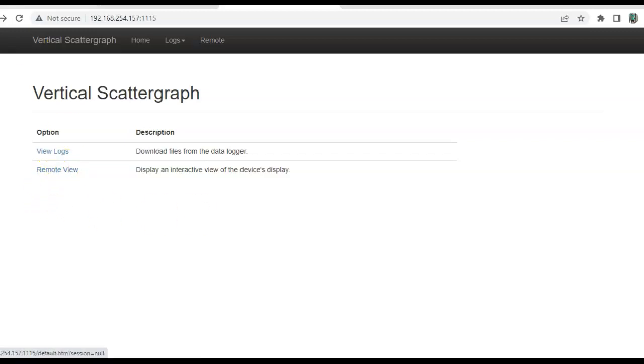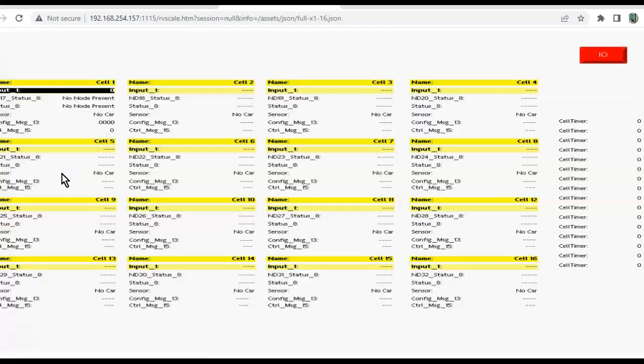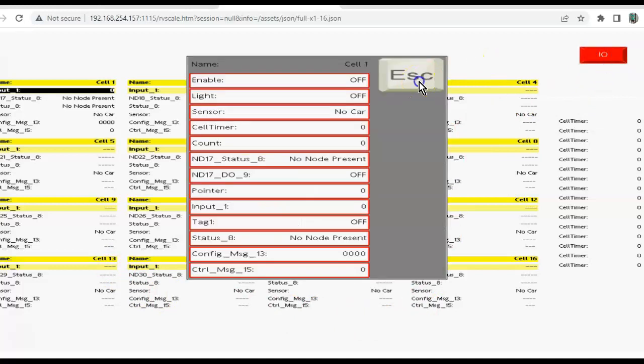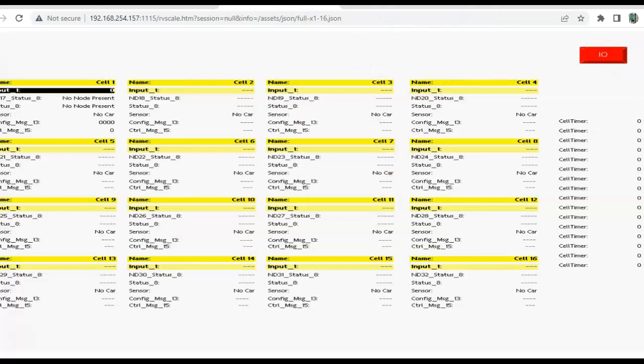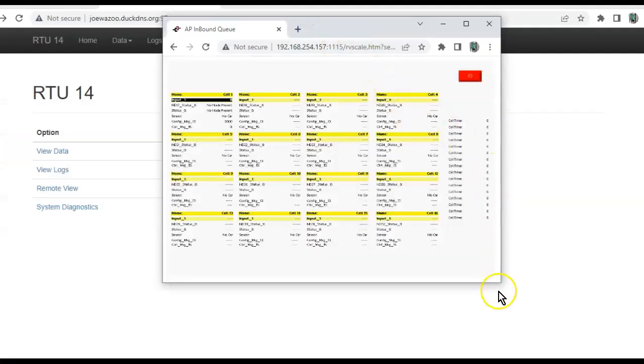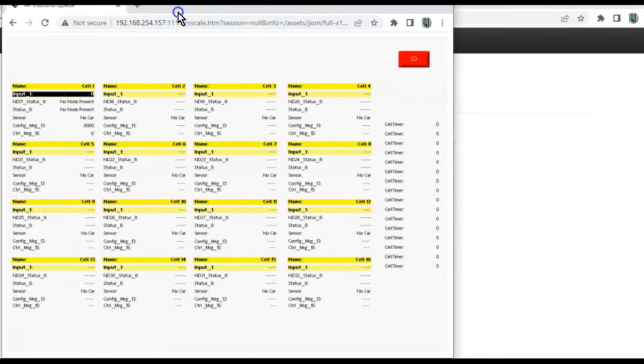All right, hit the refresh here. Let's see if it, okay, shows what they had there. Let's go here. Okay, notice the only one I did was this one. The rest of these are all dashed lines because they're still looking at the real tags, which is perfect. And if I click the IO button here, brings up this, which is perfect. Let me make this so this is a floater. I noticed that my recording window might not be showing this as well, so I'll make this a little bigger.